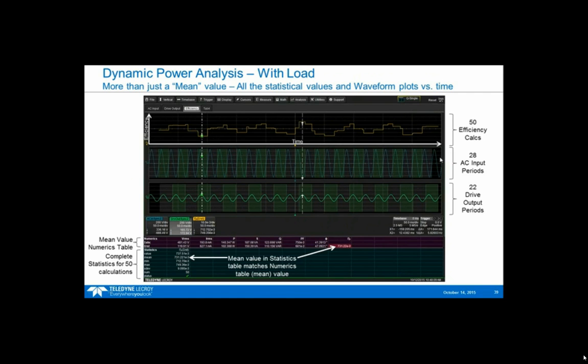Here, I counted 28 AC input periods and 22 drive output periods, and therefore there's a total of 50 efficiency calculations. One thing to note here is there really is no standard for how you calculate efficiency on a cycle-by-cycle basis when the input cycle is different than the output cycle. So there's no standard. We're kind of writing a rule book here and being creative. A power analyzer never had to deal with that, because it would just look at the input power and the output power and calculate an efficiency, but you would never know what the per cycle value was.